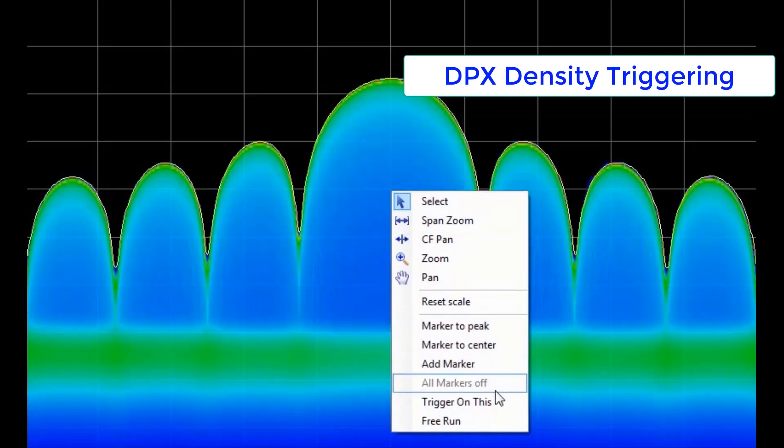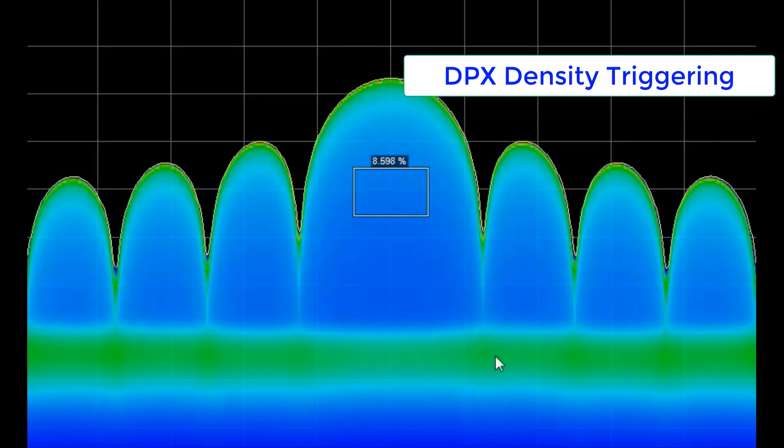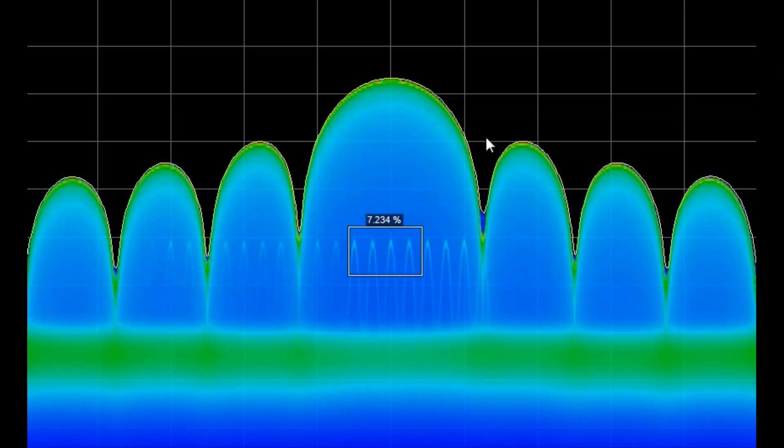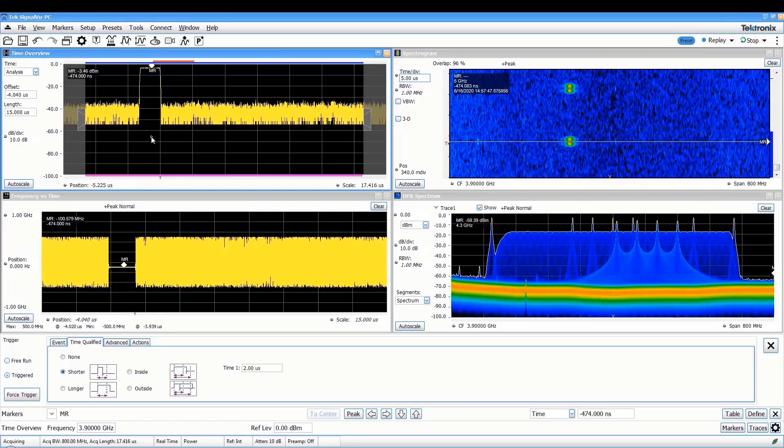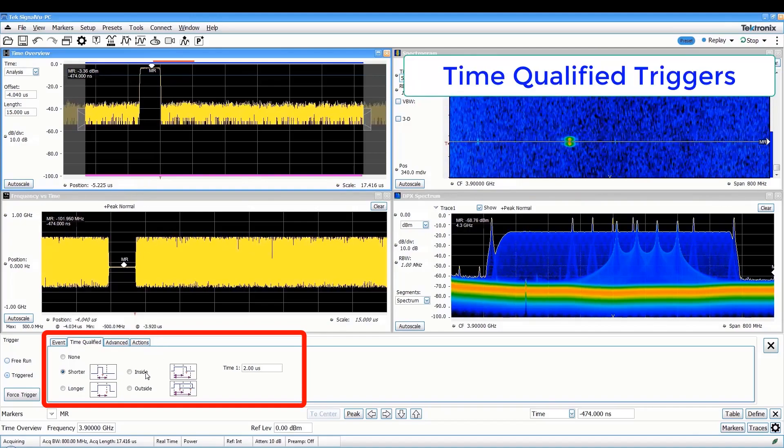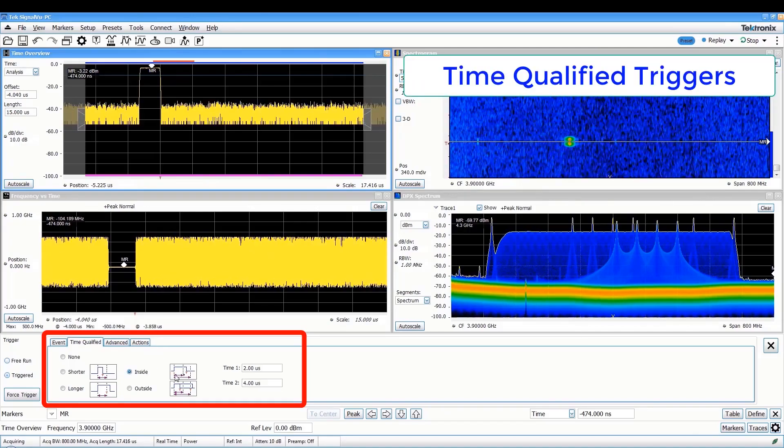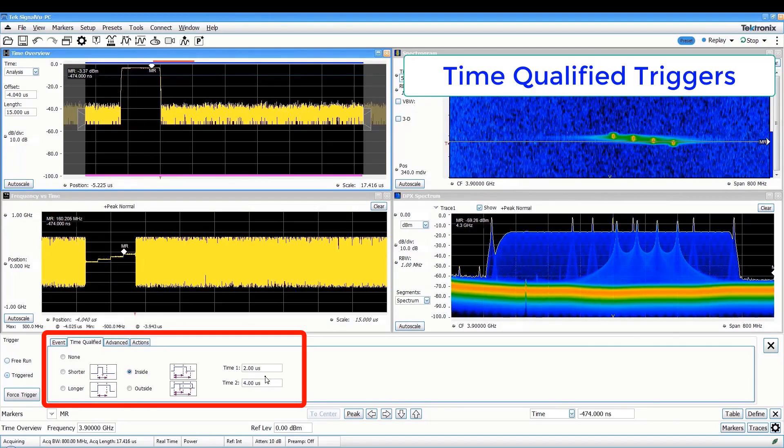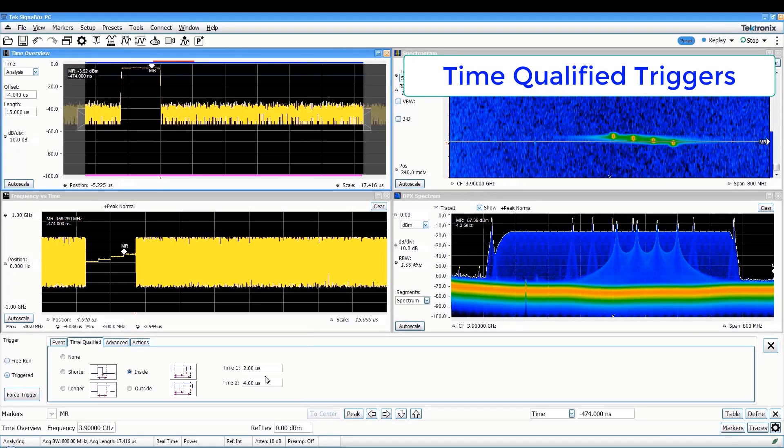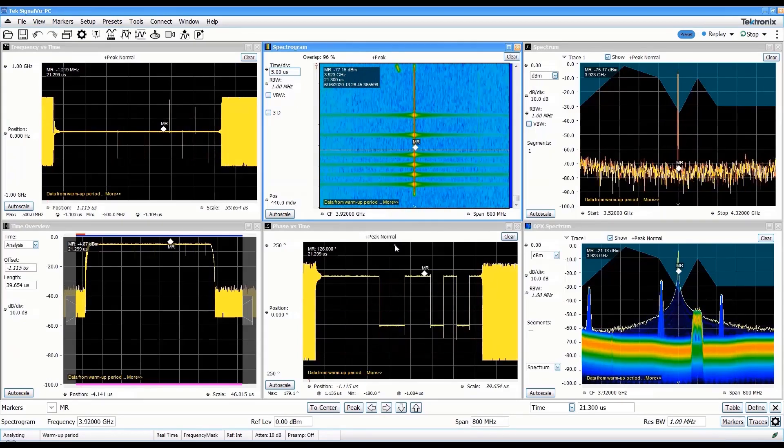The exclusive DPX density trigger is especially useful for targeting signal under signal events and other transient signals that would elude conventional trigger systems. Additional features such as time qualification round out the most comprehensive trigger system available in any signal analyzer.